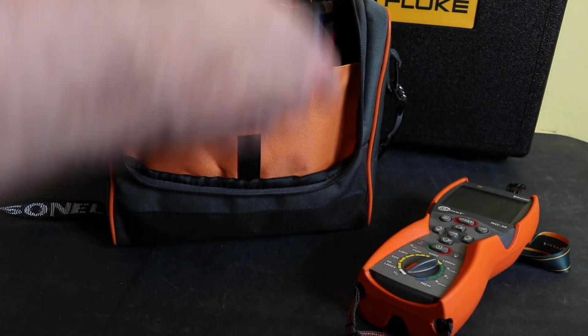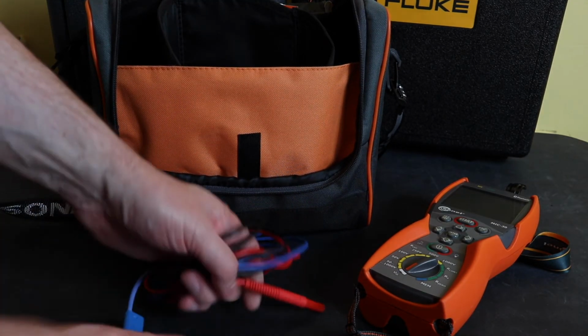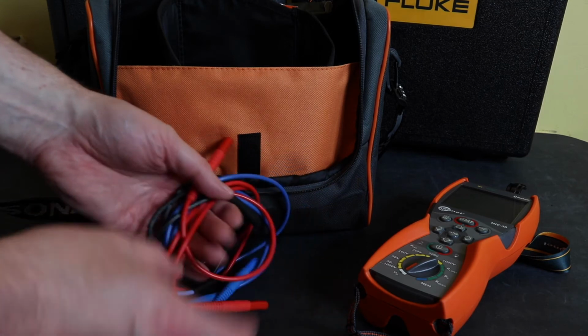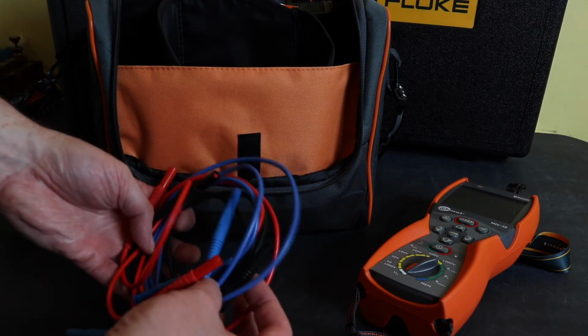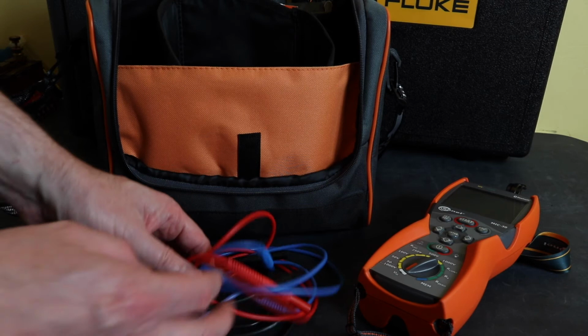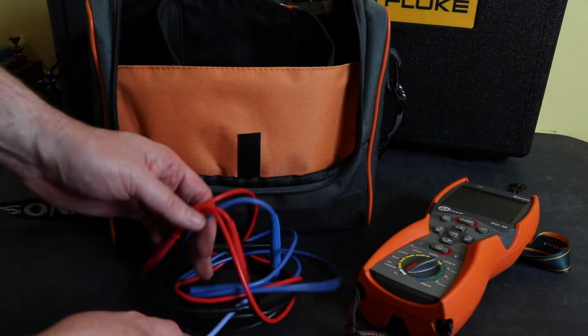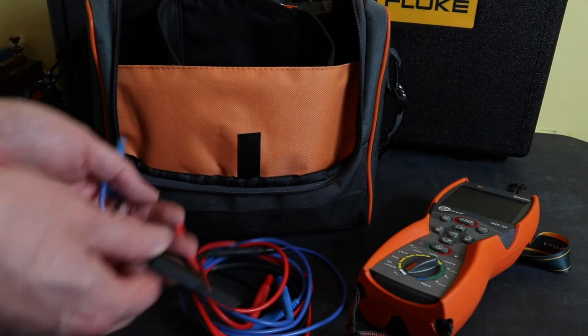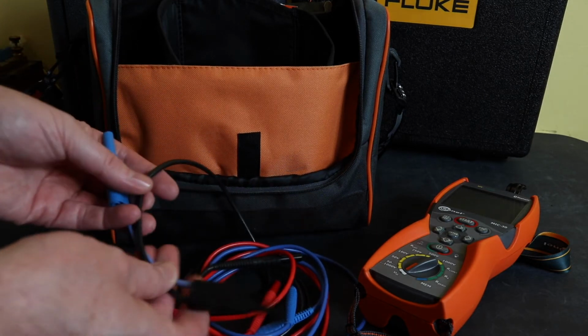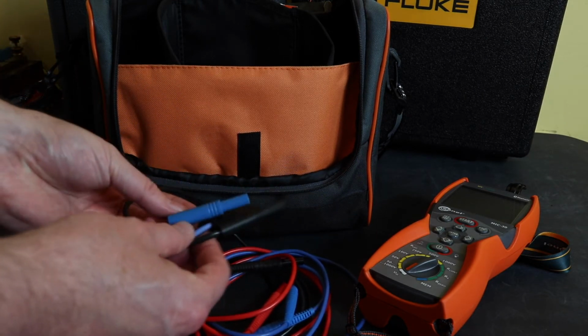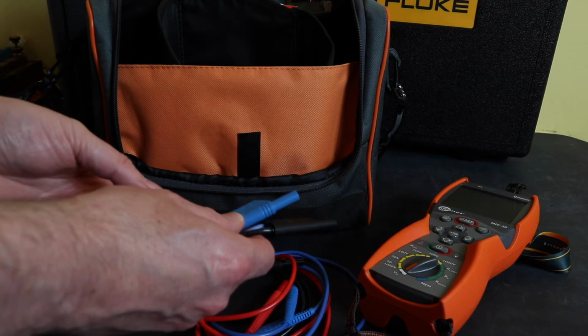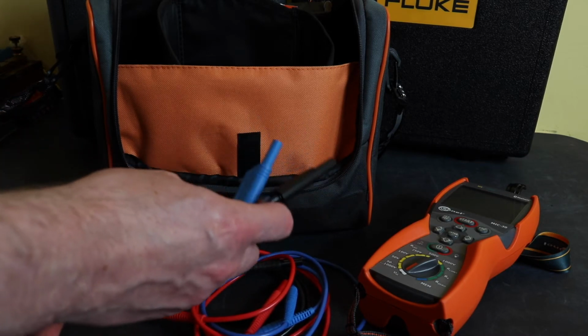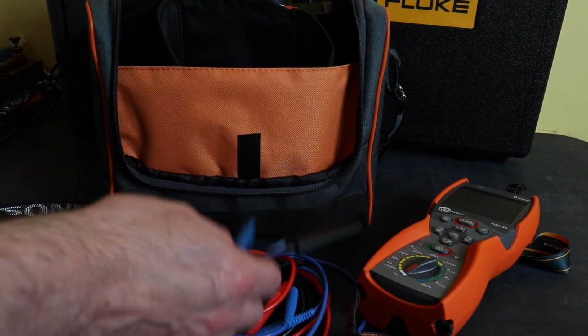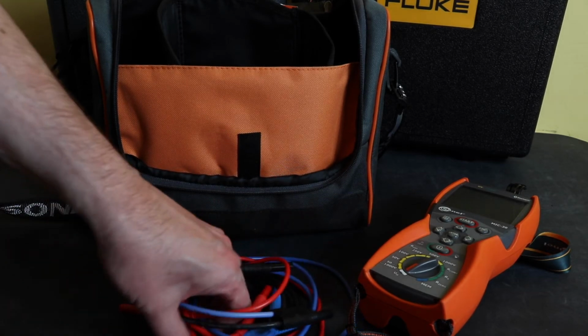And then inside you've got a set of test leads. With this instrument you get 3 test leads, the red and the black, and you get a blue test lead as well. Yeah, this black lead as well is a shielded test lead that you can use with the guard terminal on the instrument. Neither the Fluke nor the Megger have a guard terminal, so they don't have a shielded test lead.